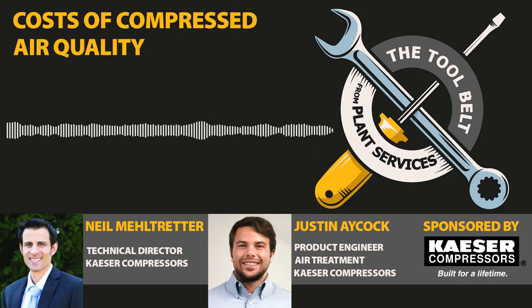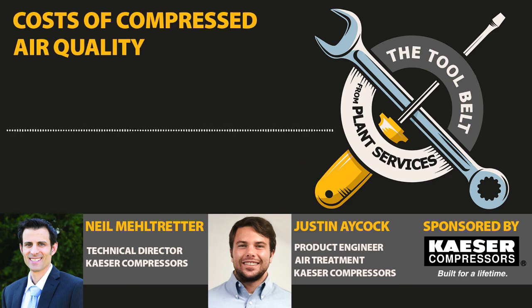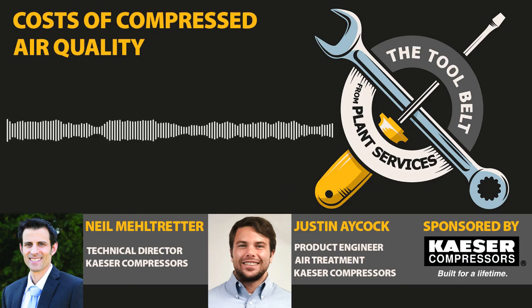And the other thing too is that I mentioned regulated uses versus unregulated uses. Having a master controller is a great way to do that, but you can also put in a flow controller to maintain system pressure downstream, or really at points of use, depending on how big those demands are. And that can also help with maintaining the operating pressure as low as possible, and potentially not affecting this air quality situation that we had in regard to the piping.